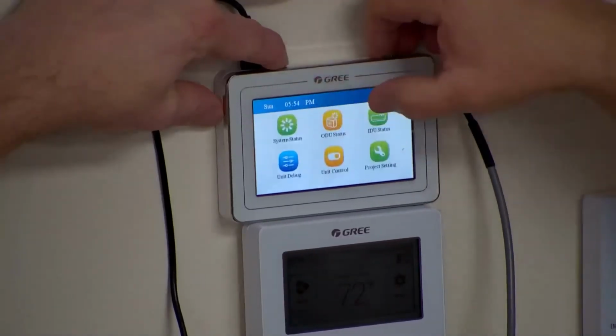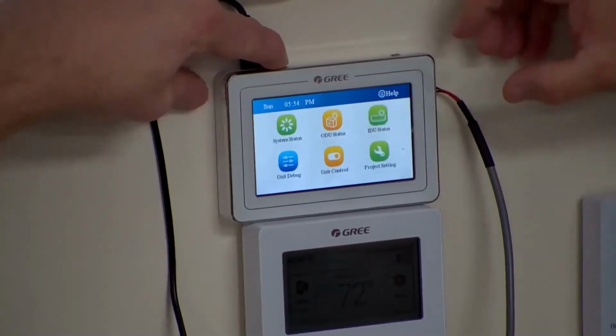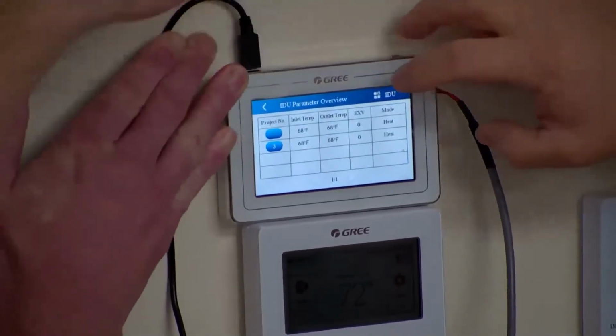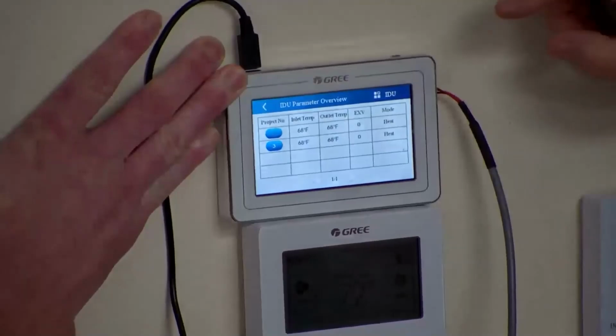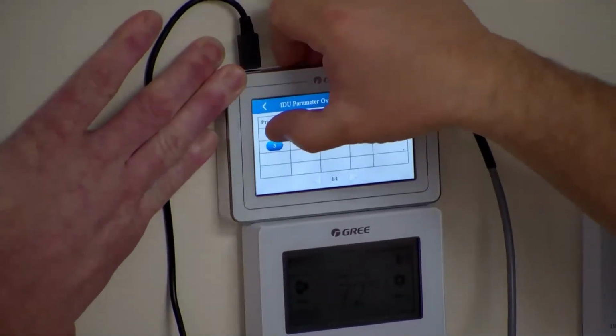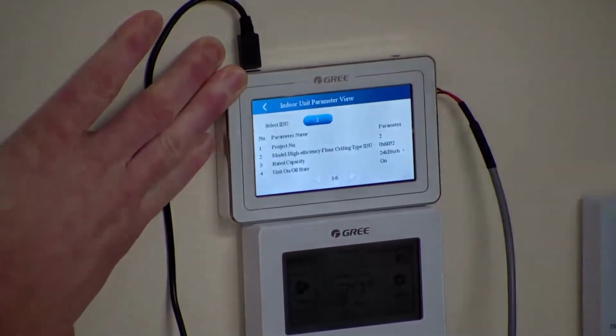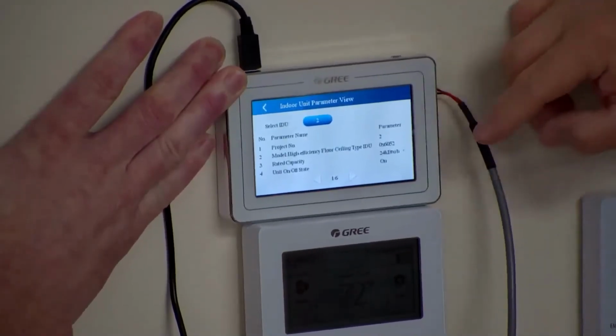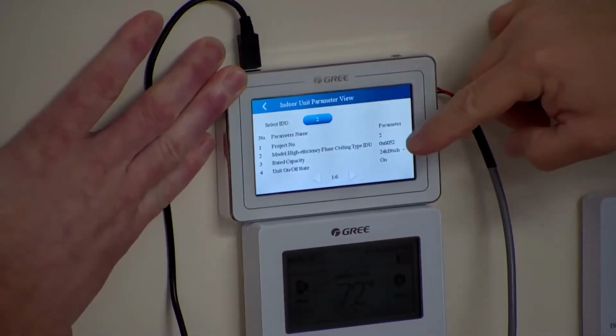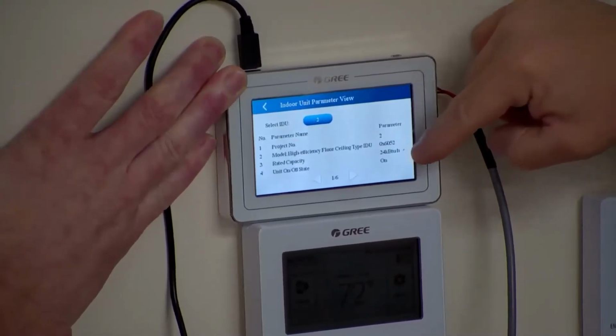Once they're on, I can go to indoor unit status. I can select which indoor unit I want to see the information on. Let's go to 2. It's telling me on project number 2. It tells me what the BTU of the unit is. It's a 2-ton.